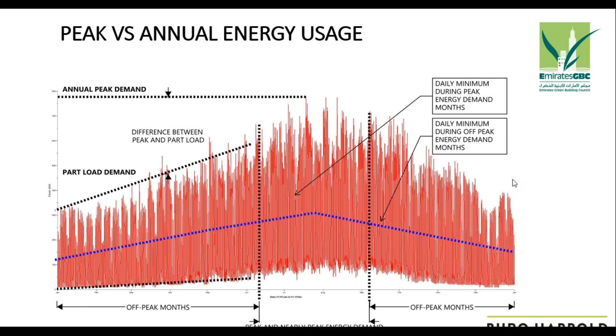An important point is that if you go down that route, you have to convey to your clients that you'd still need grid energy connections, because when it comes to peak, your actual PV usage could only possibly cover a single line that way. So that's why you need to understand peak versus annual energy usage - it helps you determine what path you want to take.